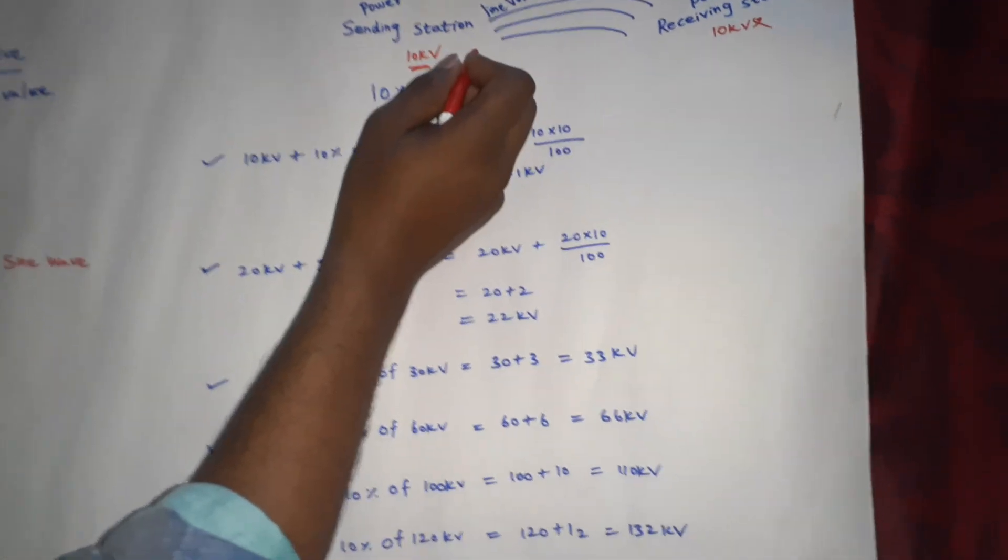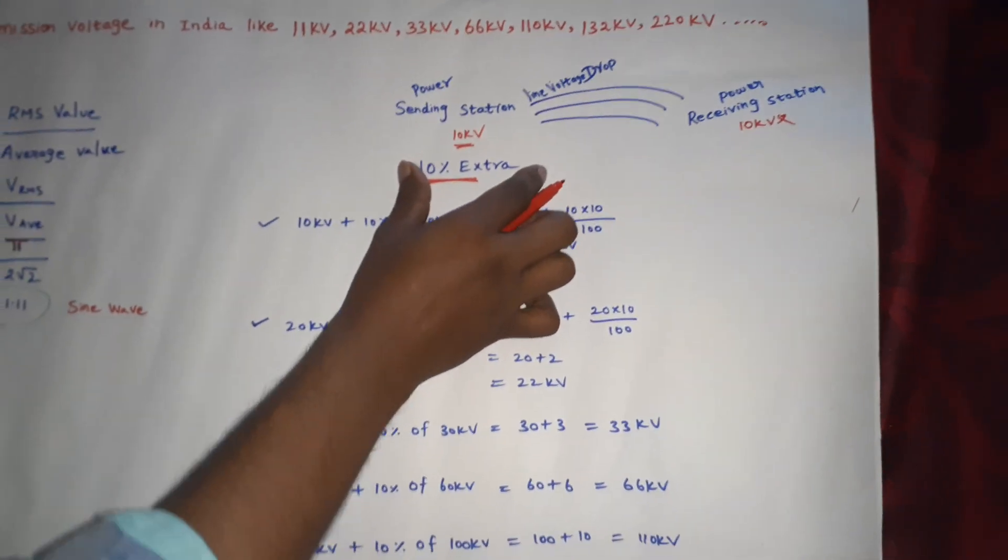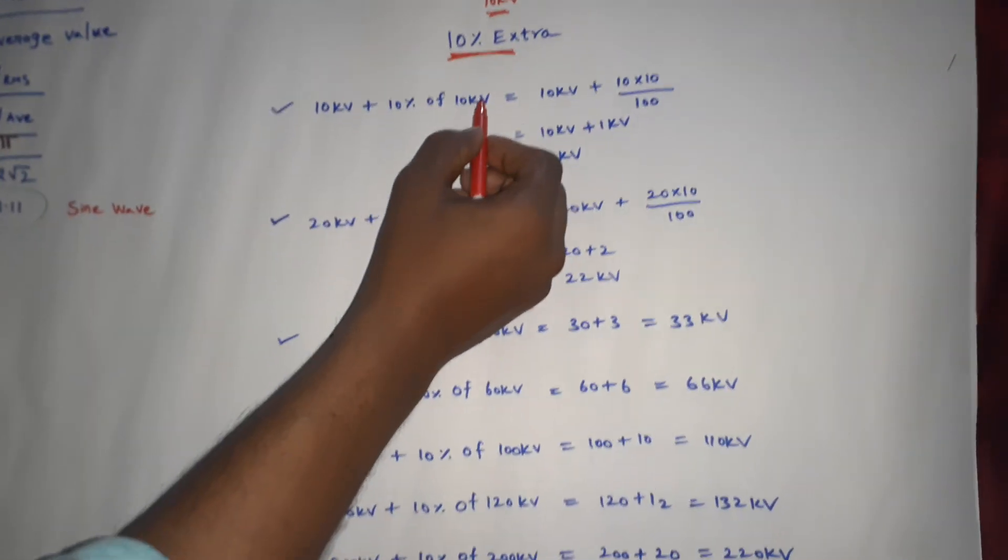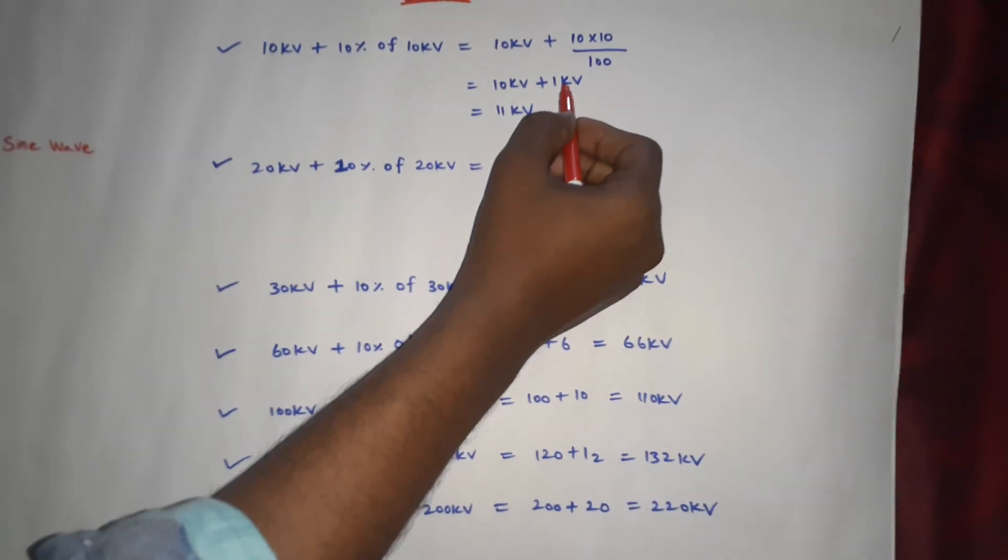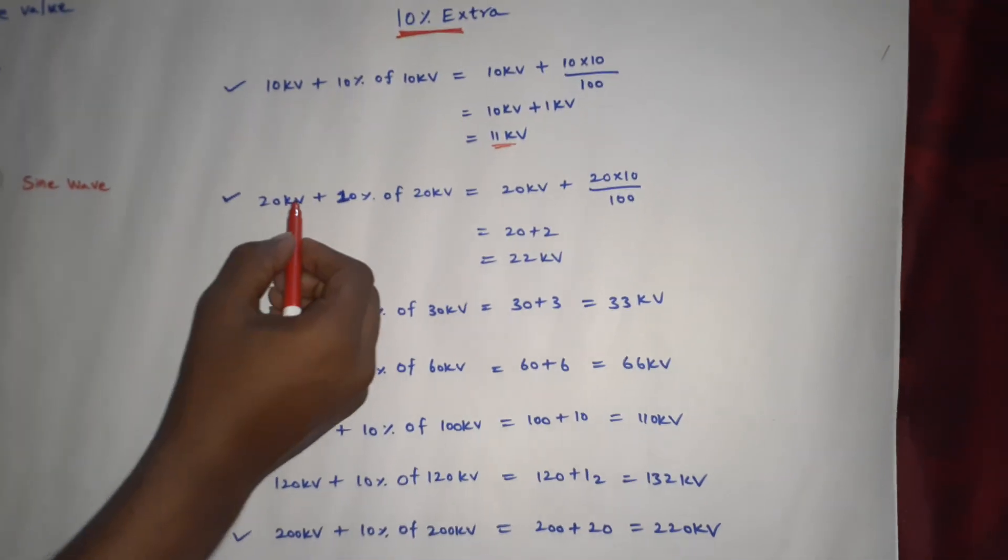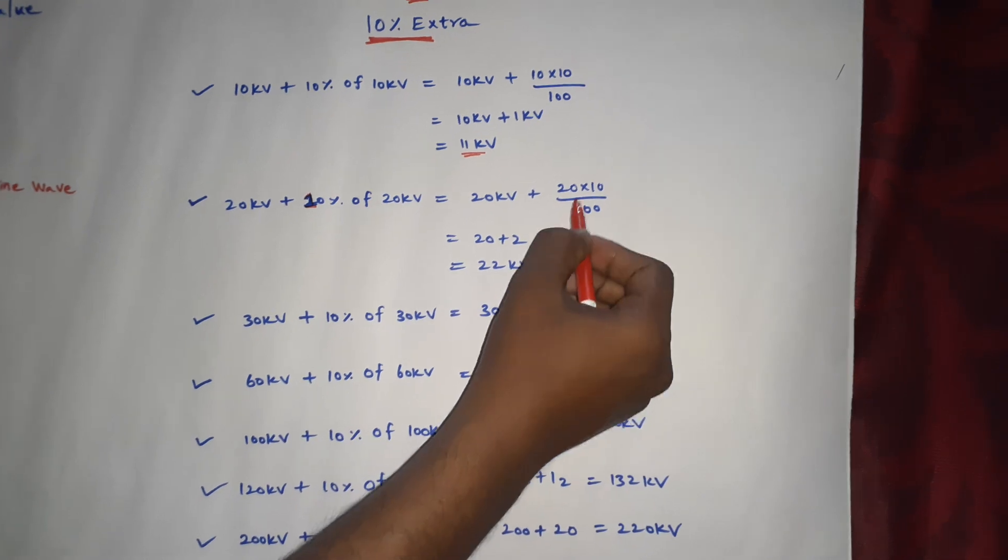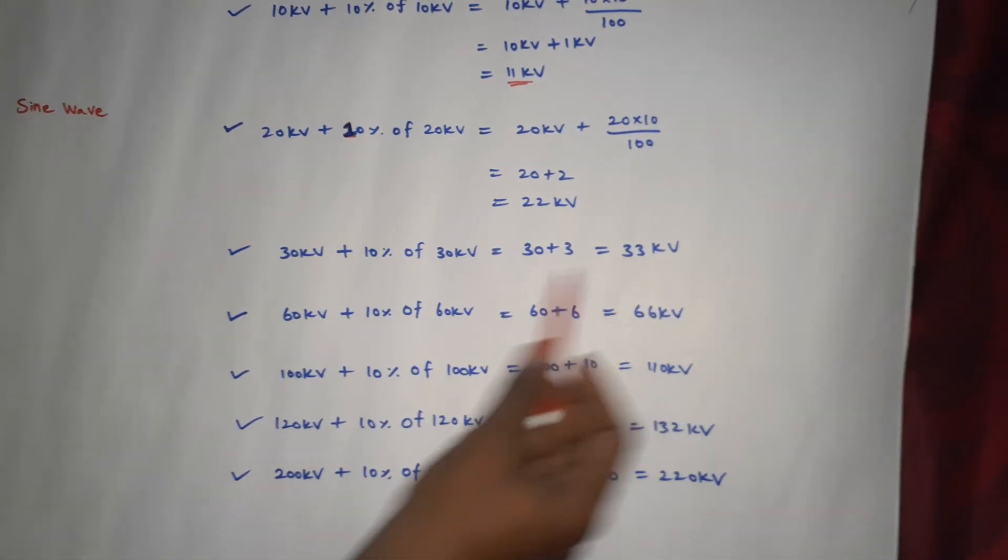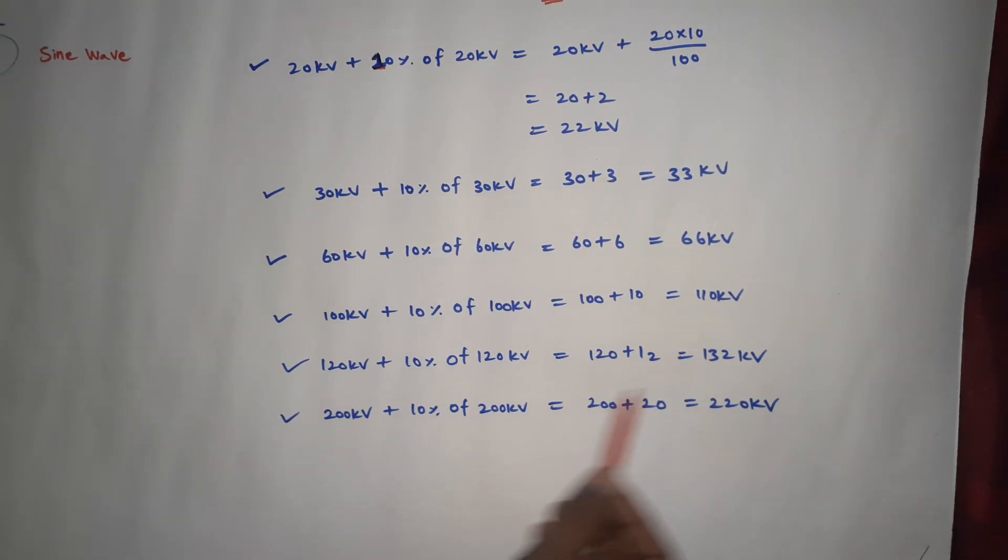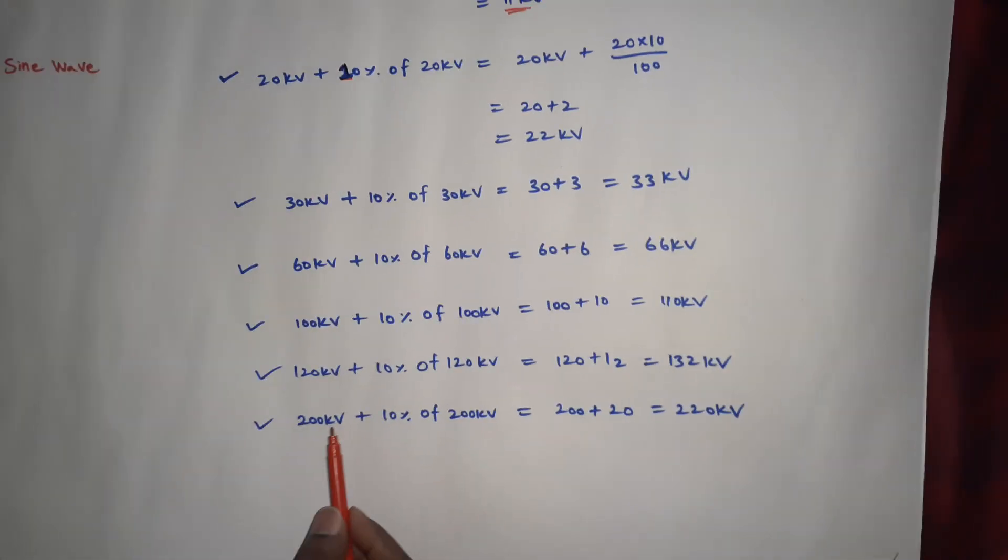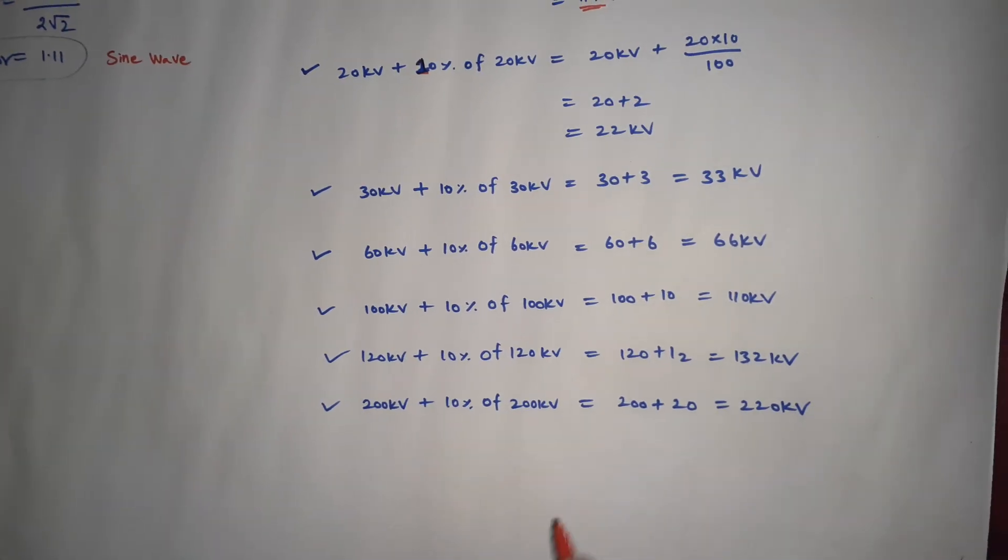If we take 10%, 20kV plus 10% of 20kV equals 20 plus 2 equals 22kV. 30kV plus 10% equals 33kV. 60kV plus 10% equals 66kV. 100kV plus 10% equals 110kV. 120kV plus 10% equals 132kV.